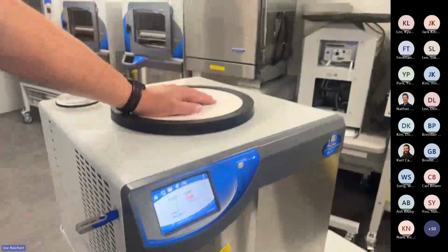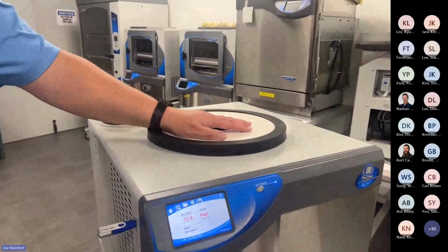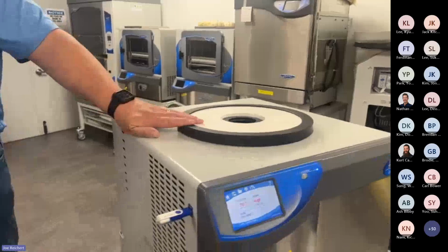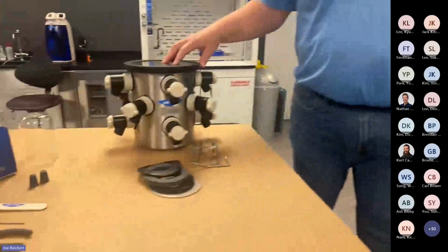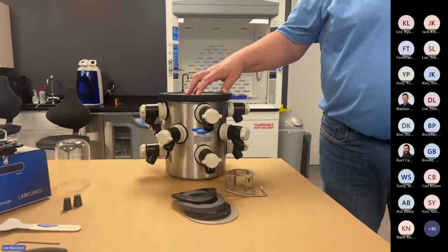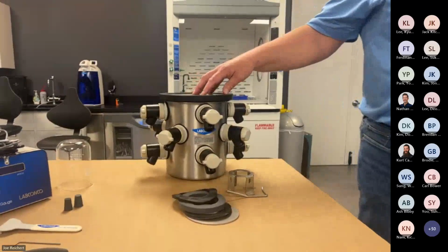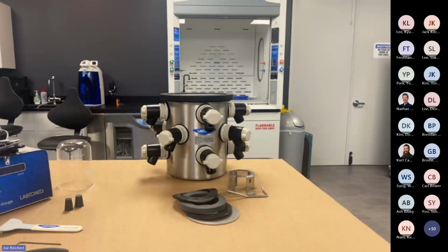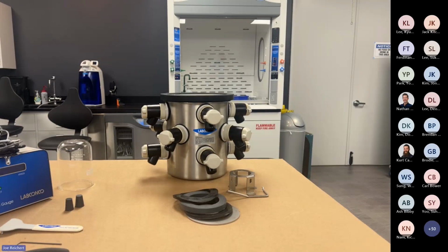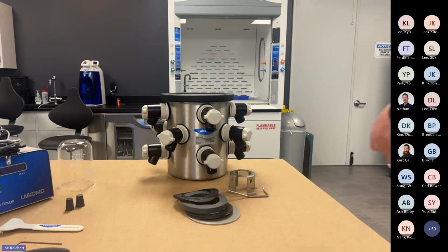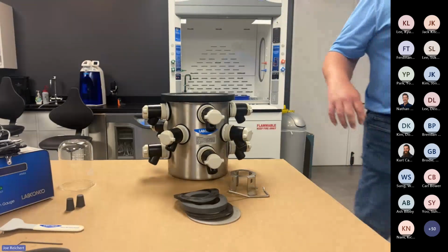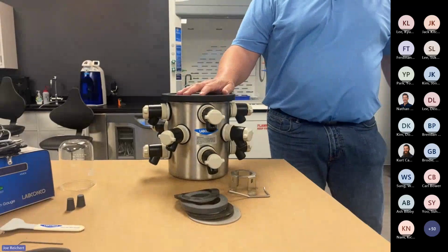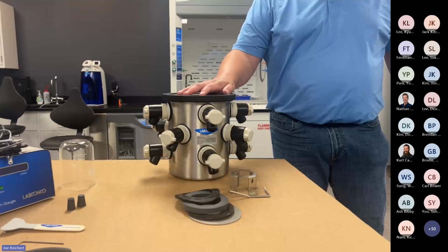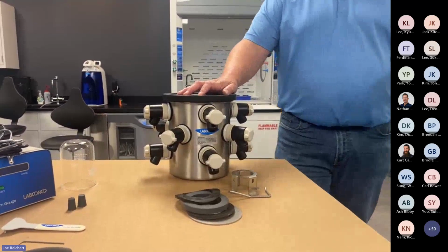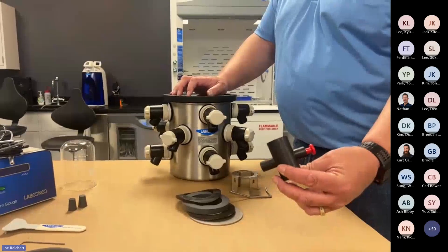But the one thing we never know is where the leak is. Is it in the chamber or is it in the freeze dryer? So the first thing to always try to figure out is, where do I need to spend all my time? You may have a vacuum pump that's not working properly, which, if you don't have a vacuum gauge, you can easily get one and test your vacuum pump. If the pump is the issue, you might spend several hours trying to find your vacuum leak and not realize that it's actually just directly in the pump itself. So if you used this is a fitting that we have in the freeze dryer.